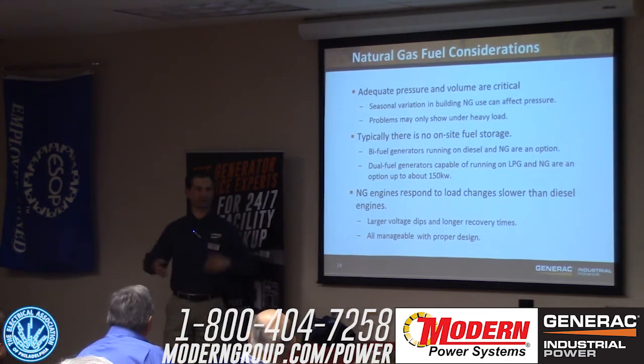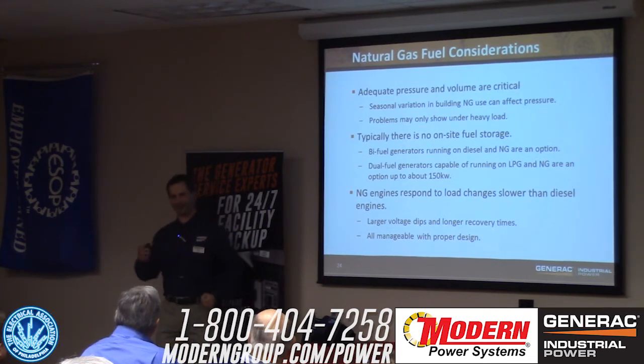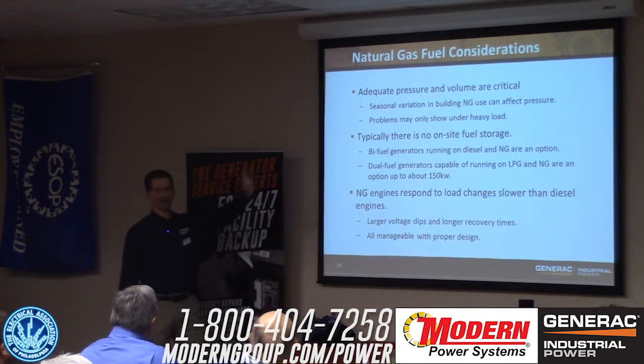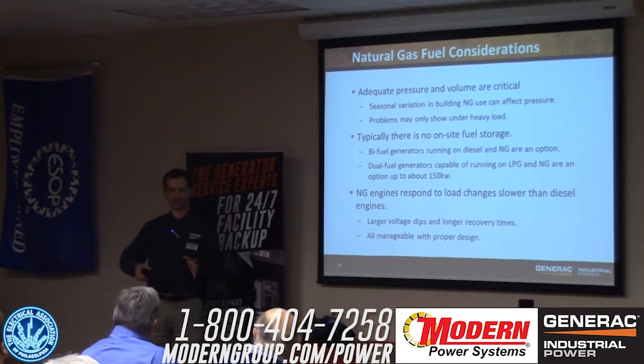If you commission a genset in the middle of summertime, life is good - I've got 11 inches on the street. You run that same genset in January when all the furnaces are running, and I've got 6.5 inches - now that's not enough for the genset. They have packaged gas boosters, so if somebody gets into a jam with that, we can fix it.